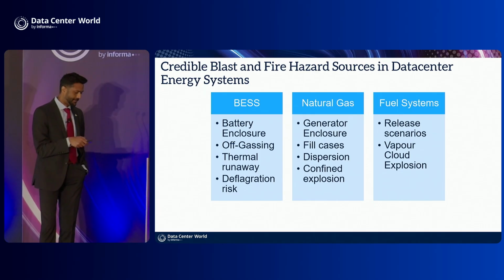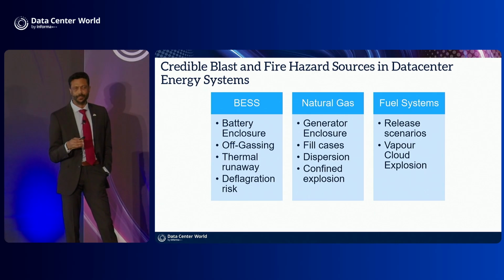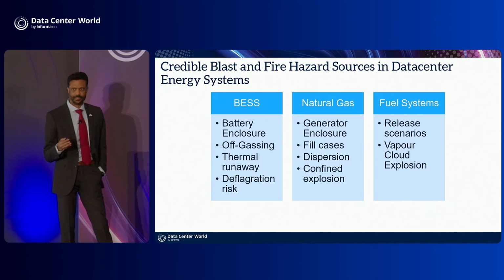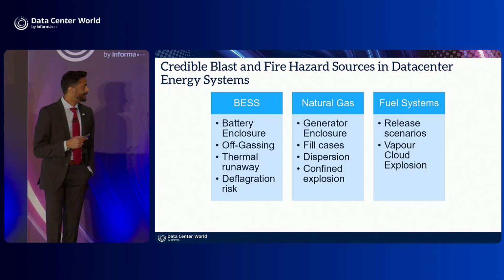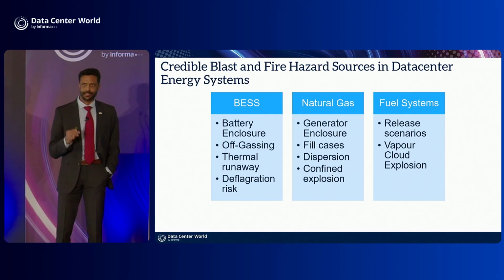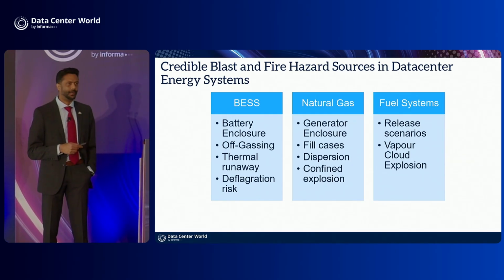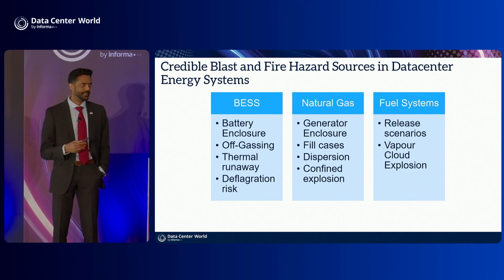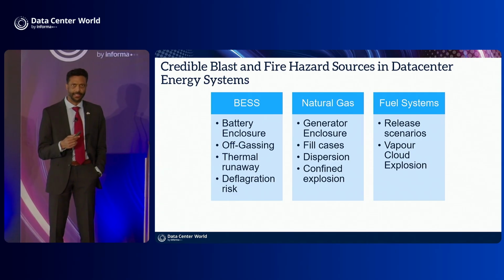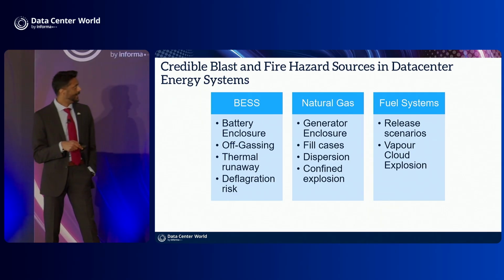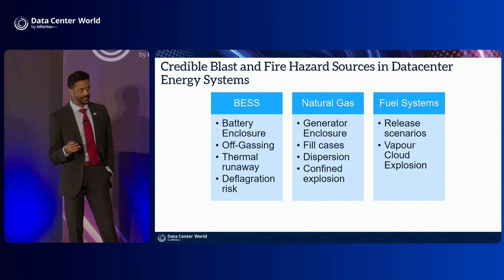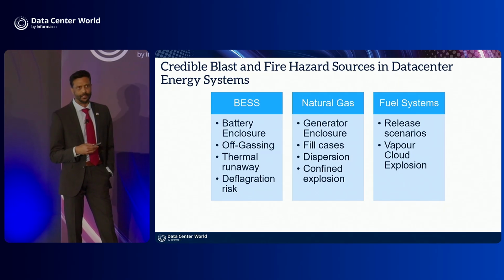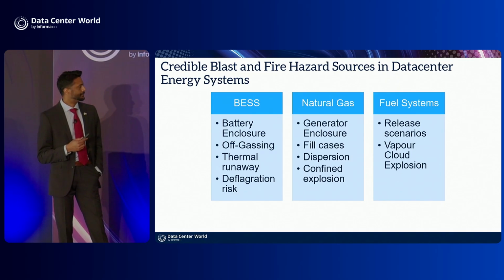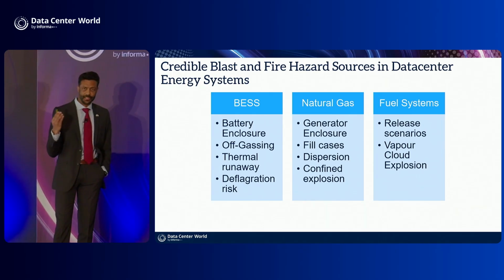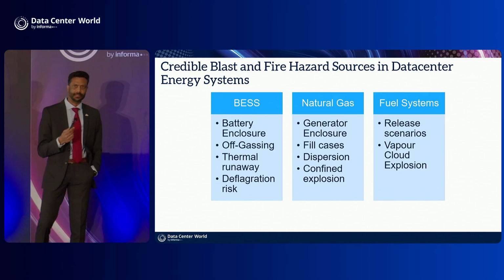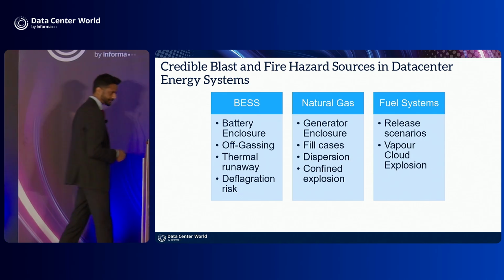A similar case can be shown for natural gas. These generators are typically enclosed because they're external to the data center hall. Any leakage of natural gas in this enclosure can cause a fill case, leading to a confined explosion, which is typically much more powerful than an open vapor cloud explosion. Lastly, the fuel systems can lead to a vapor cloud explosion, which is a gas leakage that forms a cloud, which can catch ignition from any source and lead to a high pressure and impulse event onto the data center infrastructure.